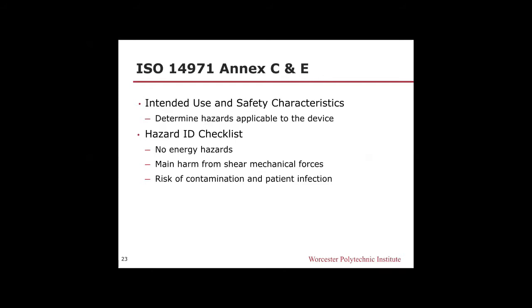So we then looked at the ISO standard for Annex C and E. C was the intended use and safety characteristics. So this was helping us brainstorm and determine hazards applicable to the device. And then Annex E was the hazard ID checklist. So we went through the list of all the different types of hazards and listed out which ones our device fell under, or which hazards may fall under it.